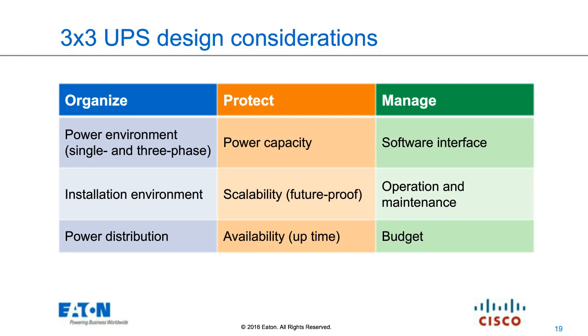To the point of redundancy or reliability, that's where this availability piece is coming in, or total uptime. Eaton has a number of solutions that can increase the availability of the total system by increasing the reliability of a UPS. It's a machine, and machines do from time to time break down. That's nothing unique. But there are considerations you can take up front, such as using intrinsic N+1 redundancy in the power, so that for those likely-to-fail components, they're redundant. So the actual server loads don't see any downtime at all. And with management software, you can very quickly be alerted that there's a failure. Eaton service can come out and take care of that and make your data center whole again. But the whole time that's taking place, no server loads have gone down.